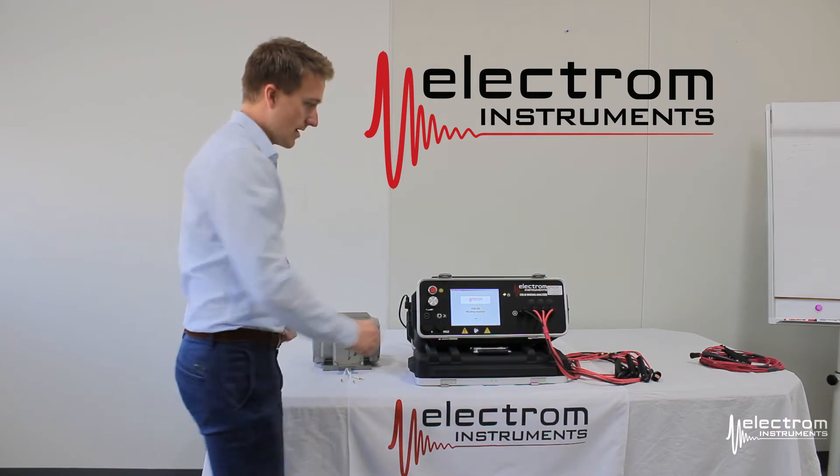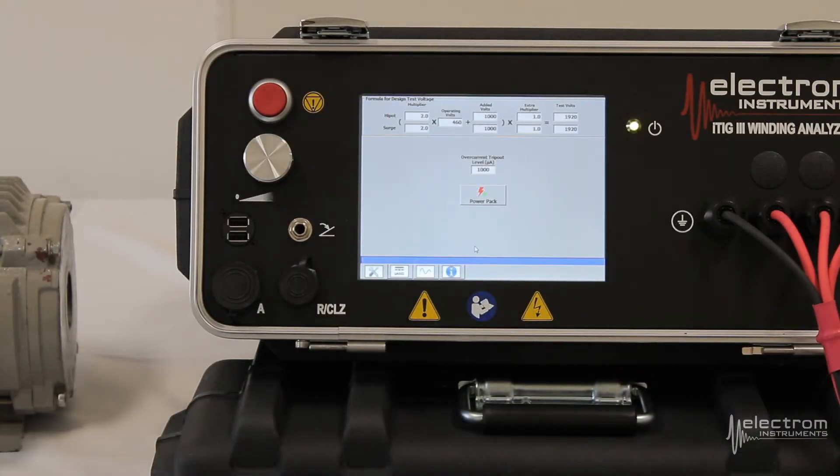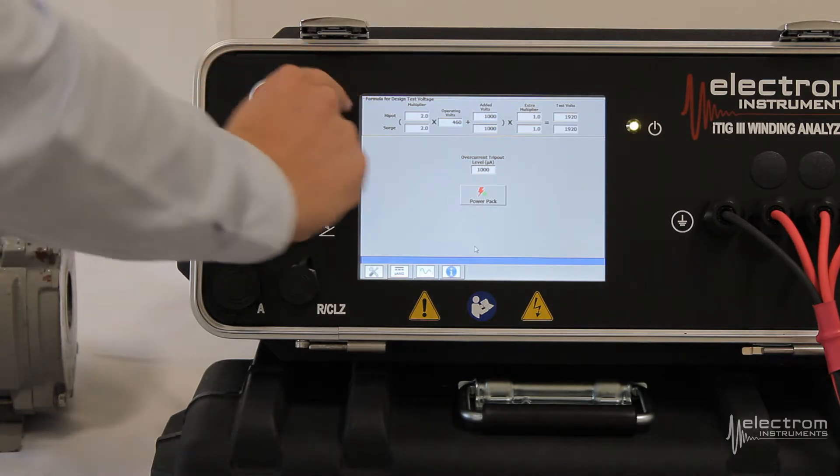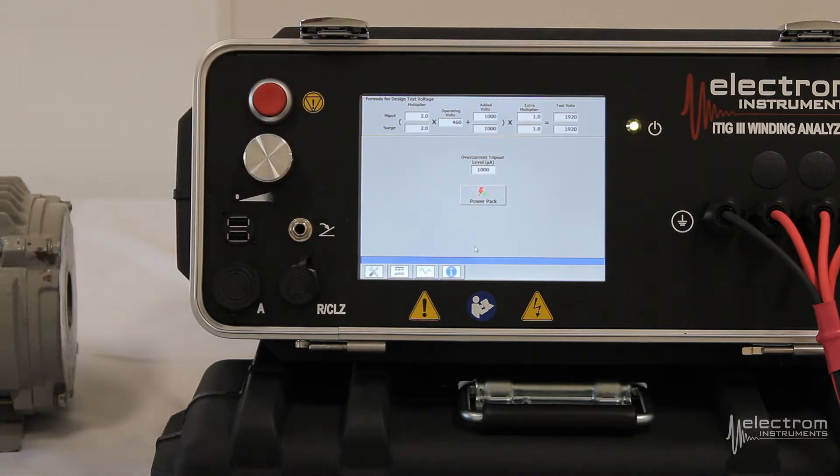To get started you click start. We get to our setup screen. We have the high pot and surge test voltage formulas. The instrument will default to 2 times the operating voltage plus 1000.